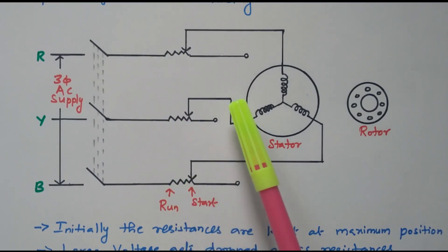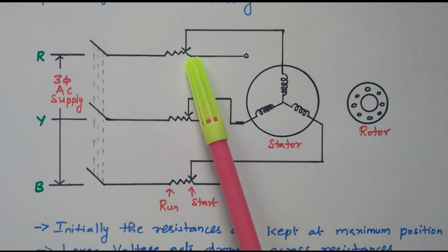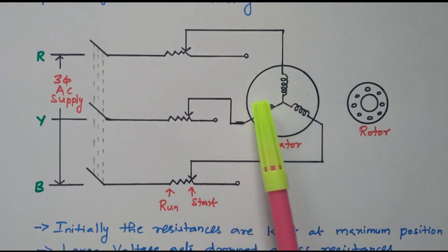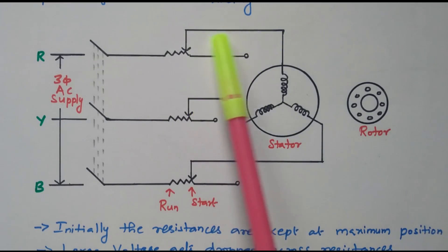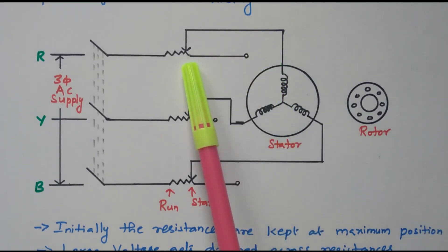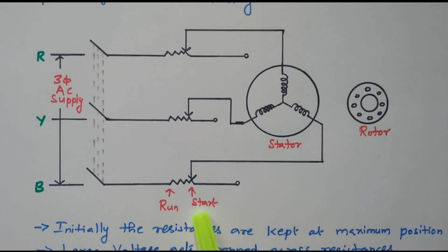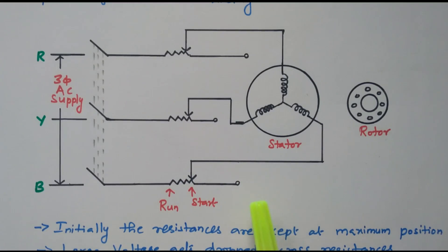At the starting position, the resistors are placed at the maximum resistance position so that the voltage is dropped across the resistors and only minimum voltage is applied to the stator. Due to the minimum voltage, the current taken by the stator is also reduced. After that, the resistance is gradually decreased by moving the position from the starting point toward the running position — that is, slowly reducing the resistance — so the voltage applied to the stator gradually increases and the current taken by the stator also gradually increases.